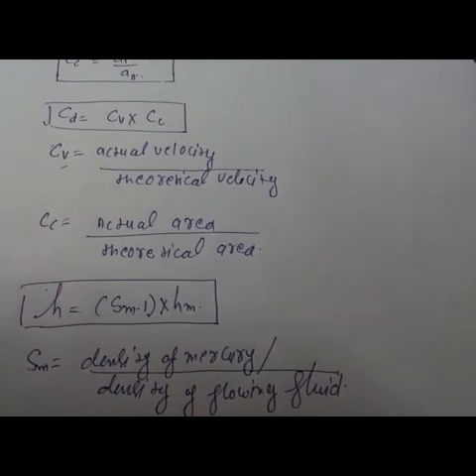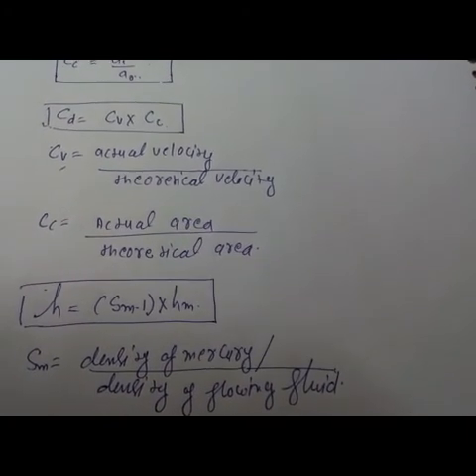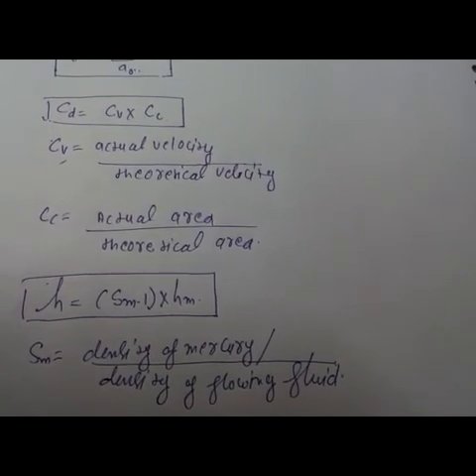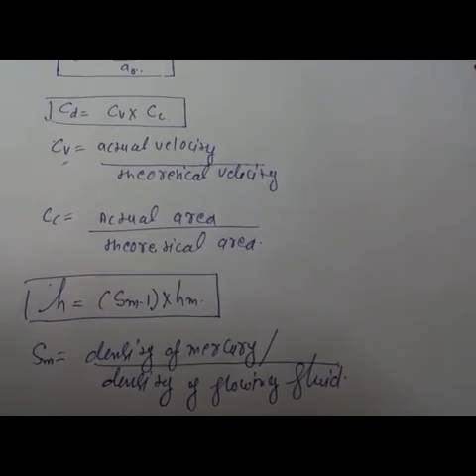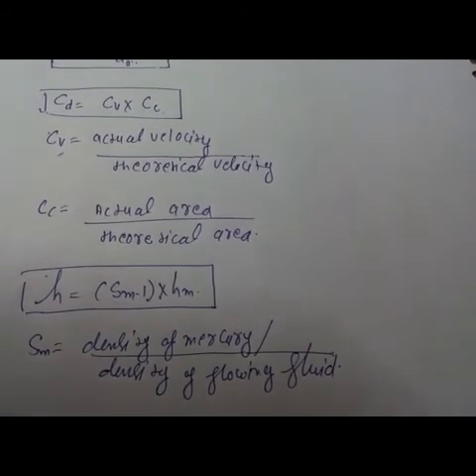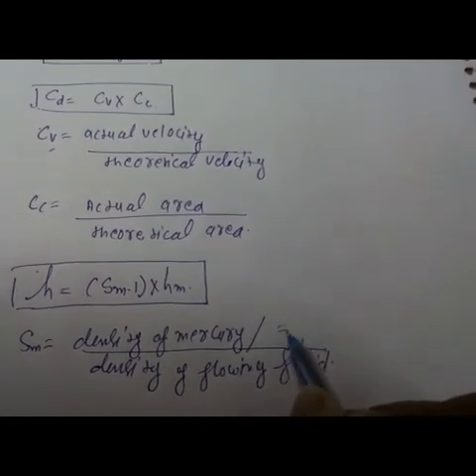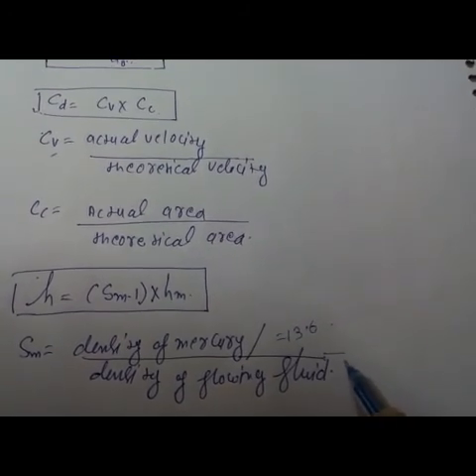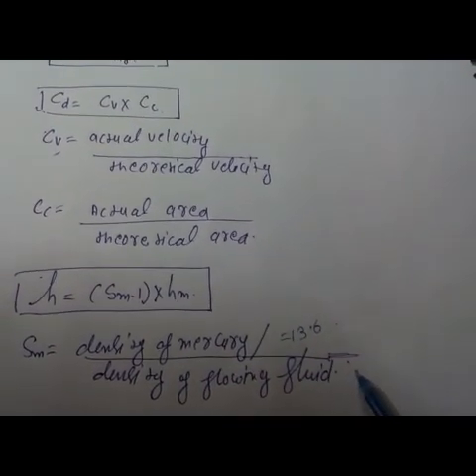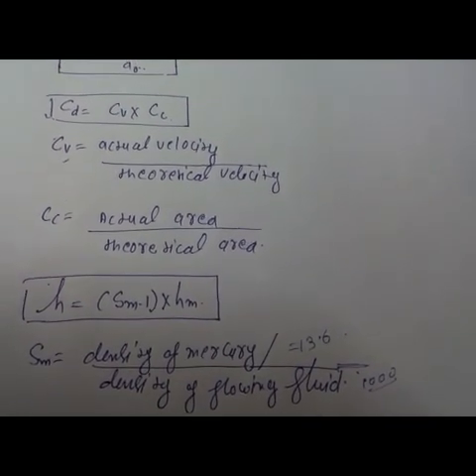The full formula of discharge is: Q equals CD into A0 into A1, divided by root under (A1 squared minus A0 squared), into root of 2gh. Since we don't directly have H, we calculate it as: H equals (SM minus 1) into HM, where HM is the head difference of the manometer fluid and SM is the density of mercury divided by the density of the flowing fluid. The density of mercury is 13.6 times that of water. If the density of the flowing fluid is not given, we take it as the density of water, which is 1000. Using this you can calculate the discharge or the coefficient of discharge.